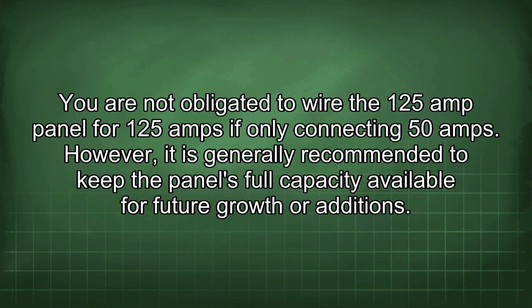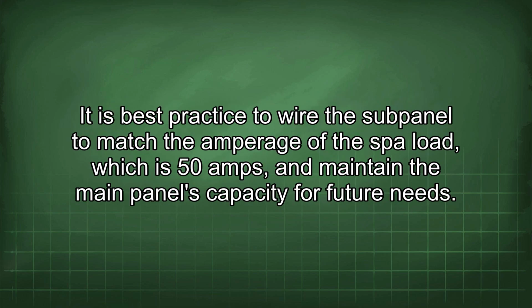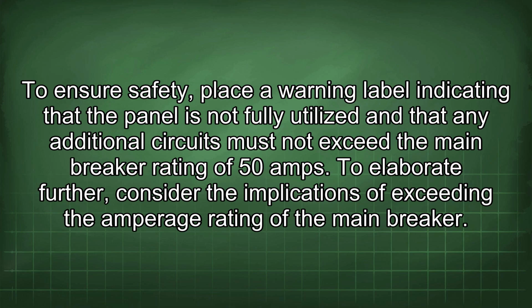You are not obligated to wire the 125 amp panel for 125 amps if only connecting 50 amps. However, it is generally recommended to keep the panel's full capacity available for future growth or additions. It is best practice to wire the subpanel to match the amperage of the spa load, which is 50 amps, and maintain the main panel's capacity for future needs. To ensure safety, place a warning label indicating that the panel is not fully utilized and that any additional circuits must not exceed the main breaker rating of 50 amps.